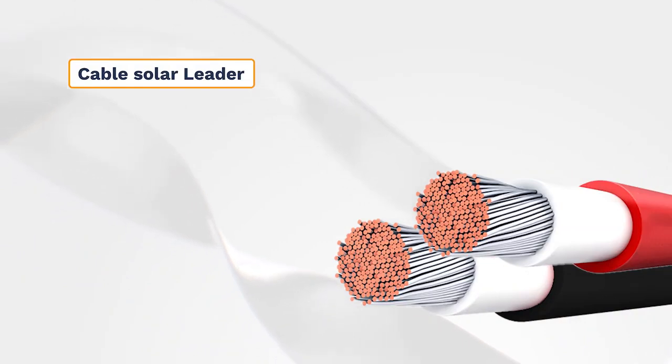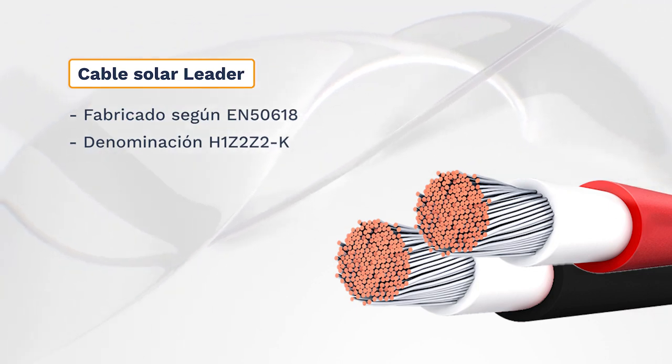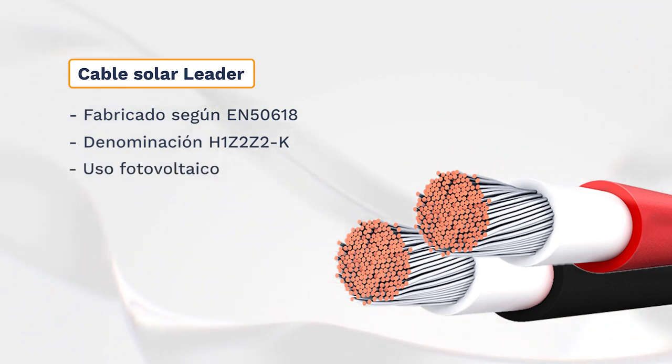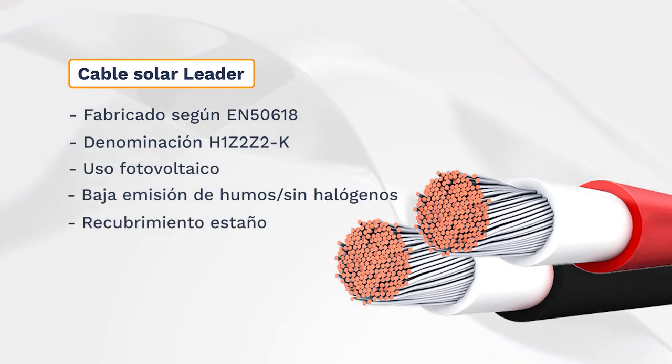Technical data. This solar cable is manufactured according to the latest European standard EN 50618, and with the harmonized designation H1Z2Z2-K. These direct current solar cables are cables specifically for use in photovoltaic systems, and in particular for direct current installations with voltage up to 1.5 kV between conductors, as well as between conductor and ground, and not exceeding 1800 volts. The EN 50618 standard requires the cables to be low smoke and halogen free, as well as having flexible single-core tin-clad copper conductors with cross-linked insulation and sheaths.